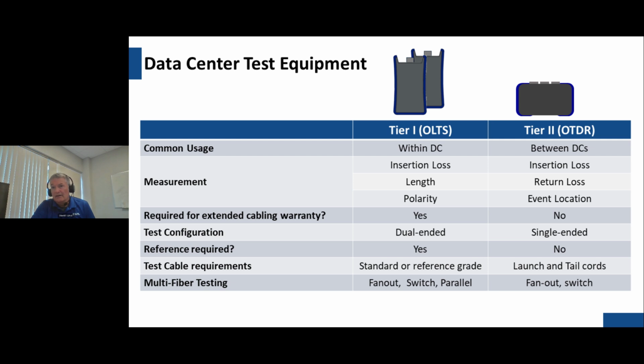And then with the OTDR—again, this is typically used for data center interconnect links, although we have seen some used for very long links within a data hall where there could be concern over extra connectors that needed to be troubleshot. These instruments will measure insertion loss, return loss, and very importantly, especially for outside plant, the ability to identify and locate an event that has high loss. An event could be a connector, a splice, or a bend in the fiber—anything that would induce higher loss than the typical loss of the fiber itself.